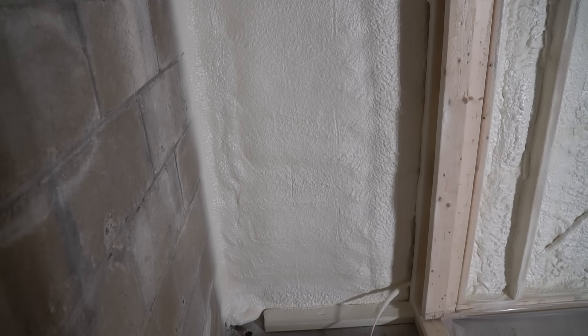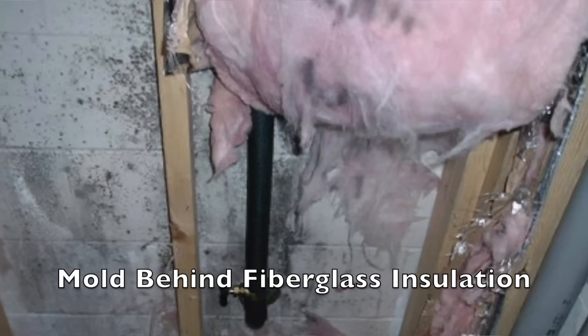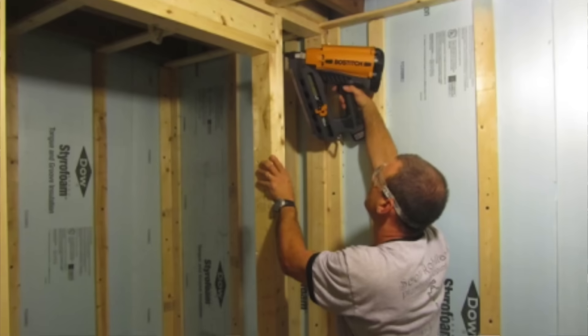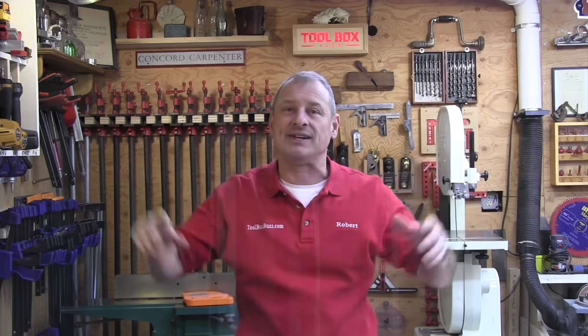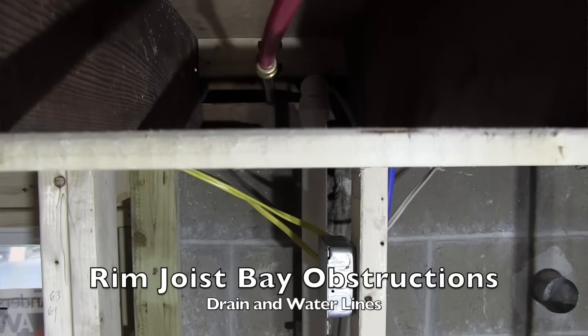Along with roughly double the R-value rating, that's one of the biggest advantages of spray foam. However, closed-cell spray foam is one of the most expensive forms of insulation on the market, and that's the biggest complaint most people have. We do not recommend using fiberglass batt or open-cell foam in basements — both require additional vapor barrier applications that often add cost and are frequently not done right. Rigid foam boards can serve as a vapor barrier and thermal insulation, but they can be difficult to achieve 100% coverage around pipes, electrical boxes, and utilities. Small irregular spaces like rim joists are extremely difficult to seal with foam board — you still need spray foam, which can cover all those irregular surfaces and achieve complete coverage.